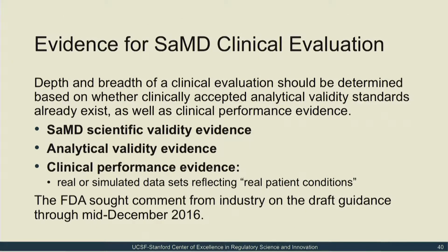Now, having established which types of software require clinical evaluation, the IMDRF further advises on depth and breadth of a clinical evaluation, which should be determined based on whether clinical accepted analytical validity standards already exist, as well as clinical performance evidence. Evaluation should be able to demonstrate appropriate scientific validity, analytical validity, and clinical performance of a software as medical device.